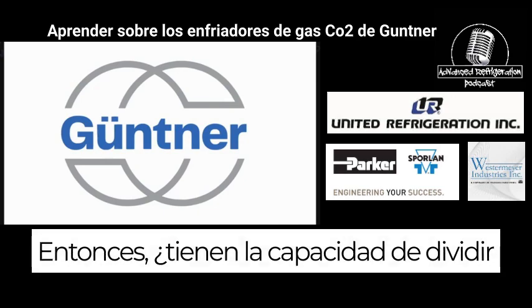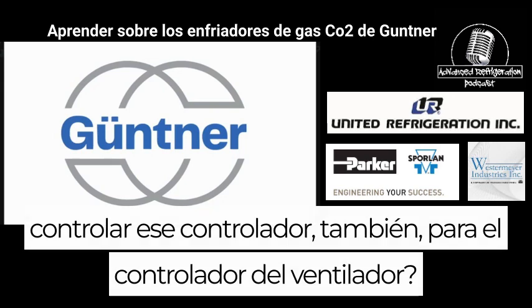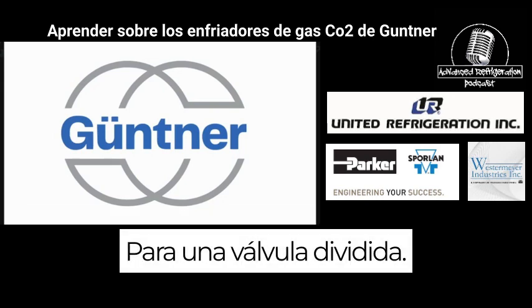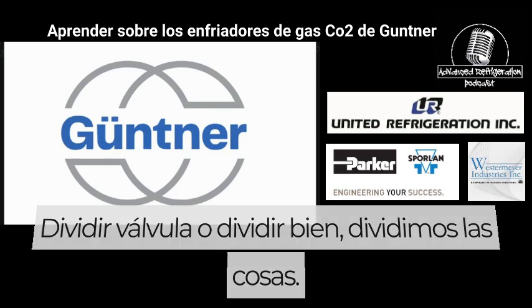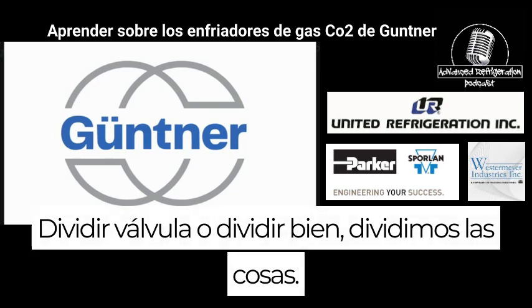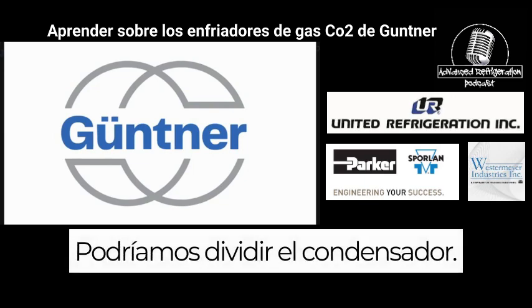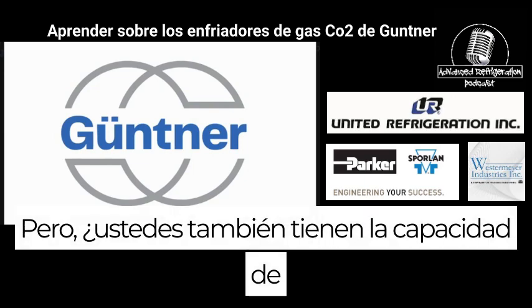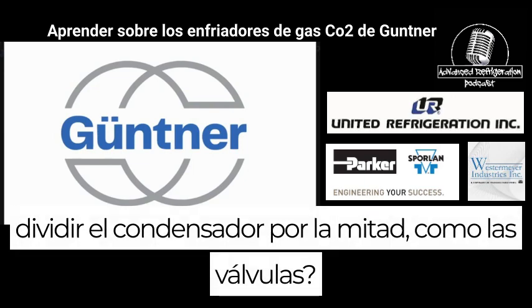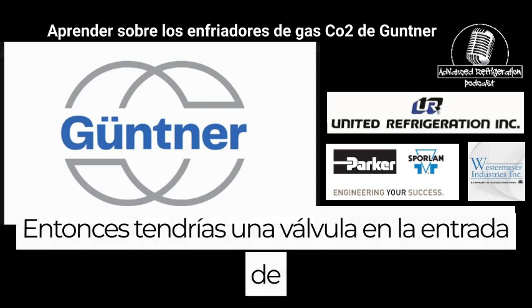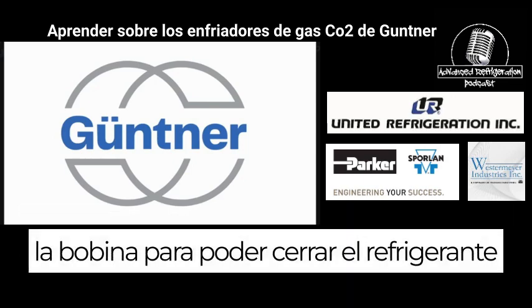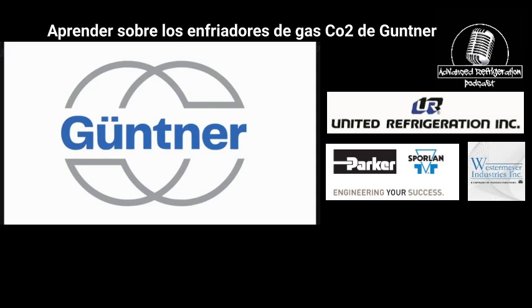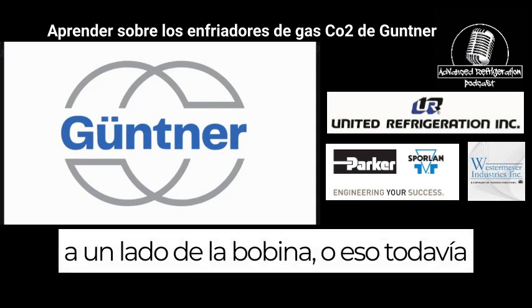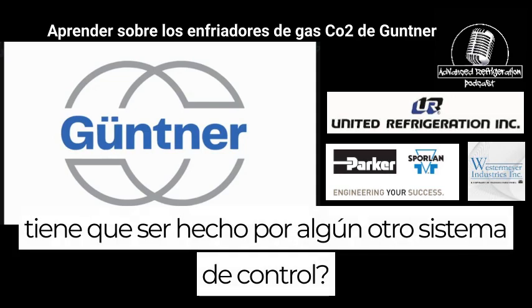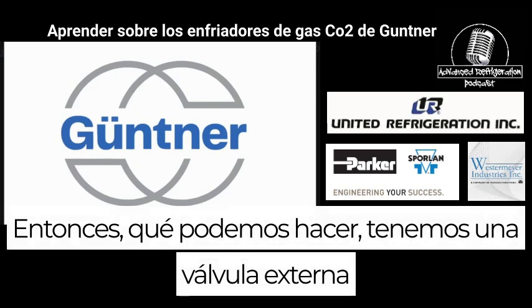So do you guys have the ability to split control off that controller too, for the fan controller? For a split valve? Split valve or split? We can split fans, we can split the condenser. But do you also have the ability to split the condenser in half with valves, like a valve on the inlet to the coil to shut the refrigerant off to one side of the coil? Or does that still have to be done by some other control system? So what we can do, we do have external valve control.